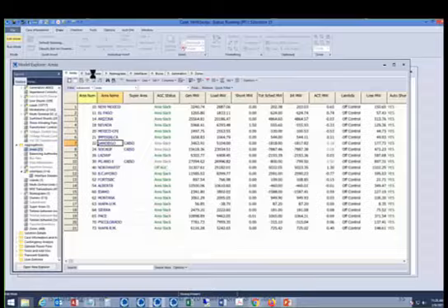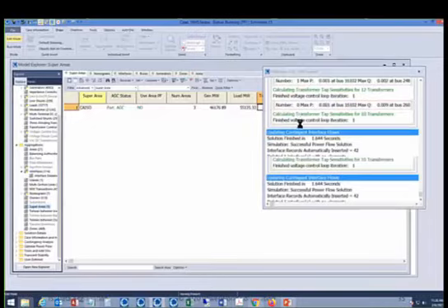So if I look at the super area records, it shows the generation, the load, and the total scheduled megawatts, so it's importing 10,500 megawatts. That's the sum of all the scheduled imports for the individual areas from other areas that are not also part of the super area. If I don't do anything right now, if I just solve the case, then it shouldn't move anything because I'm satisfying the individual areas' export obligations, so the sum is kind of still doing the same.